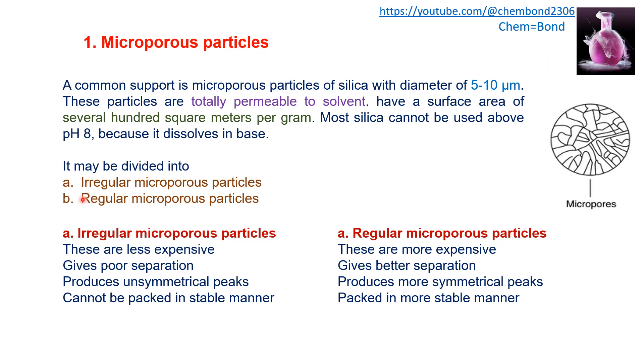Silica microporous particles can be divided into irregular and regular types, with inverse properties. Irregular particles are less expensive but give poor separation and produce unsymmetrical peaks; they cannot be packed in a stable manner due to their irregular size. Regular (spherical) particles are more expensive but give better separation, produce more symmetrical peaks, and can be packed in a stable manner due to their regular size.